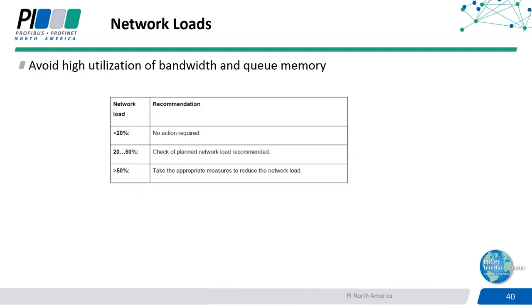So we said we could have critical network sections where you have a lot of traffic converging, or you have chatty devices on your network, such as HMIs or SCADA systems or other types of devices, using TCP/IP. So the network load should be estimated prior to your network install, as part of your design phase, or at least checked before the network is put into operation.